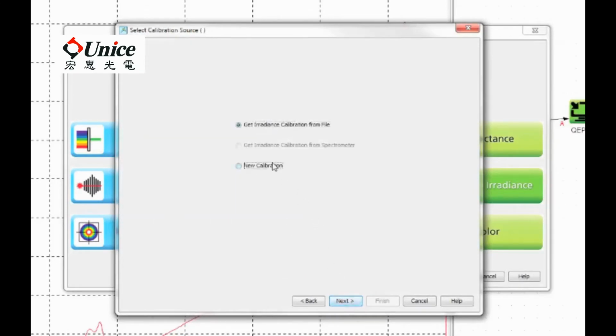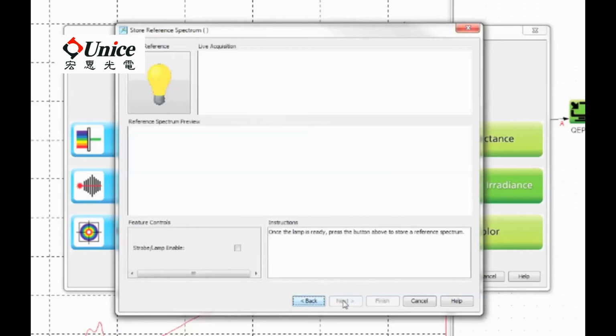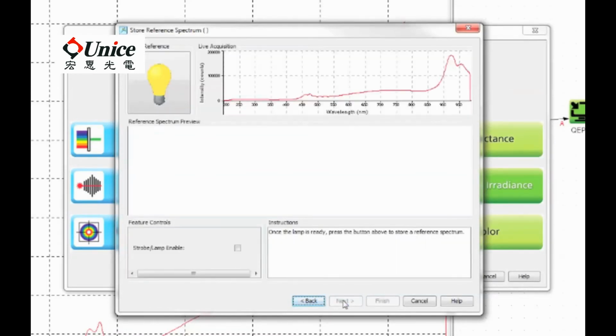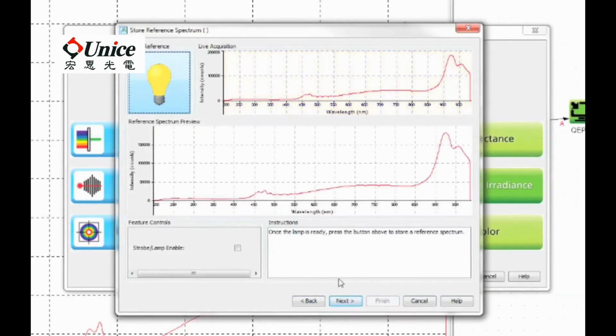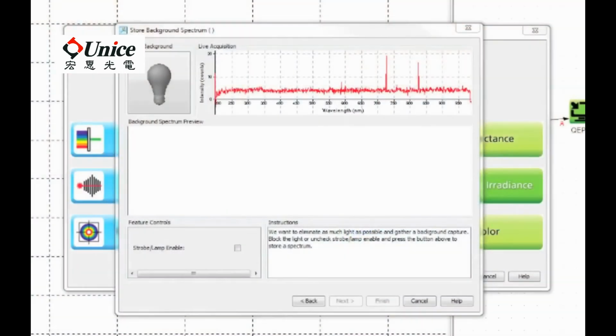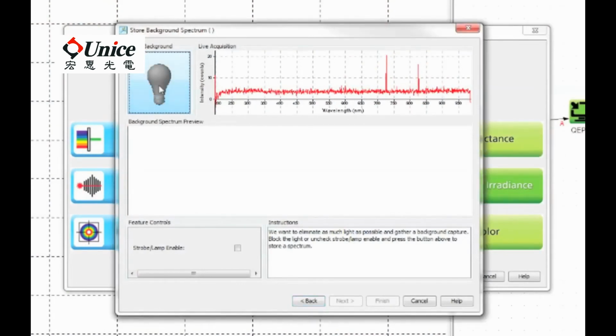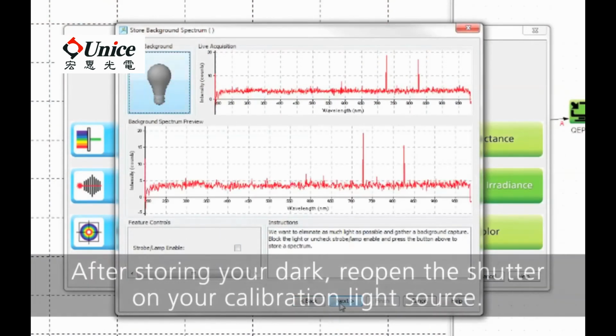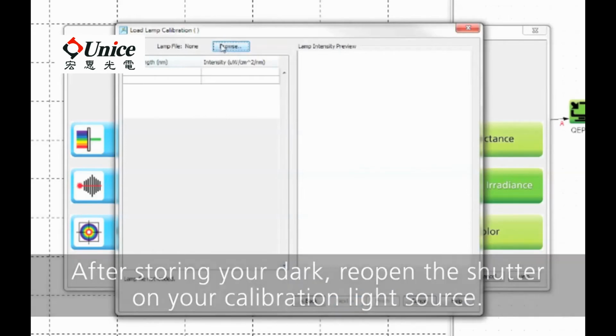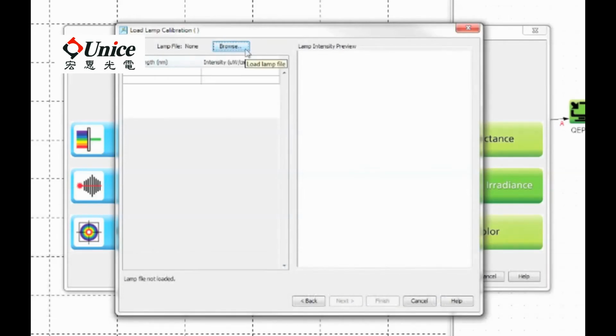Select the option to perform a new calibration. Next, you will be asked to store a reference spectrum. This is the signal that your spectrometer will be receiving when your light source is on. Click the yellow bulb to take a reference. Next, you'll be asked to take a dark measurement. Do this by closing the shutter on your light source and clicking the grey bulb icon. Then click Next. On this screen, you must get the calibration data for the lamp.